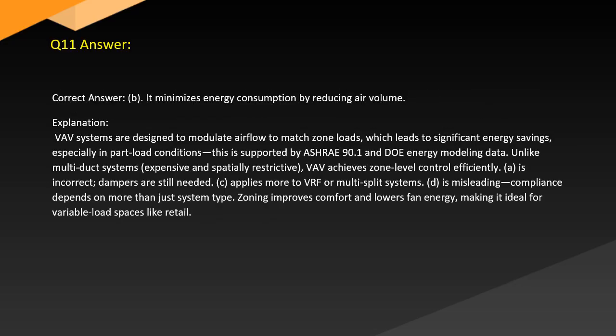Answer. Correct answer: B. It minimizes energy consumption by reducing air volume. Explanation. VAV systems are designed to modulate airflow to match zone loads, which leads to significant energy savings, especially in part load conditions. This is supported by ASHRAE 90.1 and DOE energy modeling data. Unlike multi-duct systems, which are expensive and spatially restrictive, VAV achieves zone-level control efficiently. A is incorrect. Dampers are still needed. C applies more to VRF or multi-split systems. D is misleading. Compliance depends on more than just system type. Zoning improves comfort and lowers fan energy, making it ideal for variable load spaces like retail.